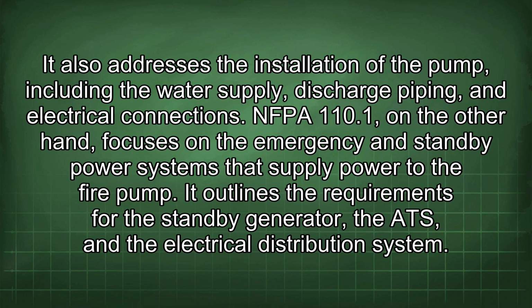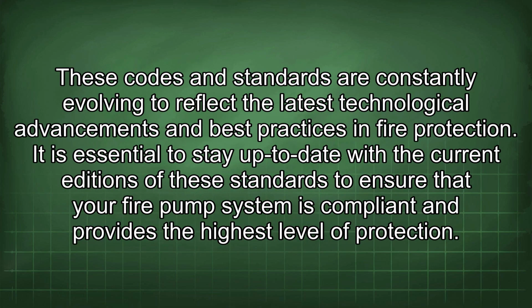NFPA 110.1, on the other hand, focuses on the emergency and standby power systems that supply power to the fire pump. It outlines the requirements for the standby generator, the ATS, and the electrical distribution system. These codes and standards are constantly evolving to reflect the latest technological advancements and best practices in fire protection. It is essential to stay up to date with the current editions of these standards to ensure that your fire pump system is compliant and provides the highest level of protection.